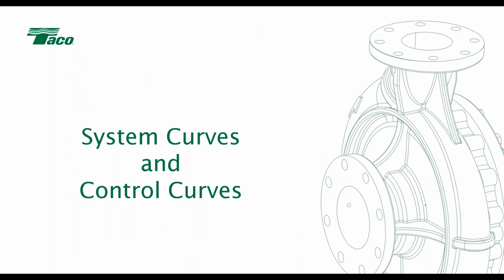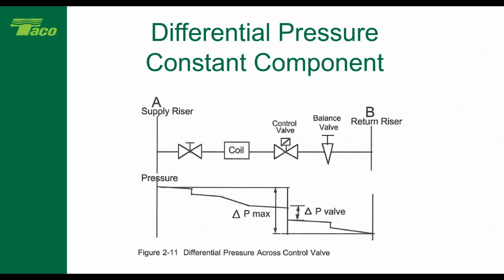So let's talk about system curves and control curves and what they really are. When we look at a system, the one thing we have to understand is that we're dealing with differential pressure. And the thing we're most concerned with is the differential pressure at our hydraulically most remote load. I'm getting tongue-tied today. And that differential pressure is a constant component. Yes, I know it's going to change as the control valve moves up and down, but it's a constant in this entire equation and in understanding how the system works.